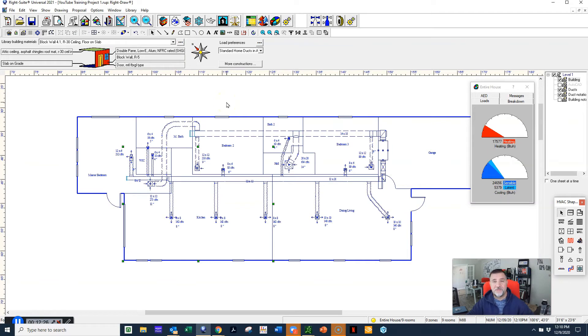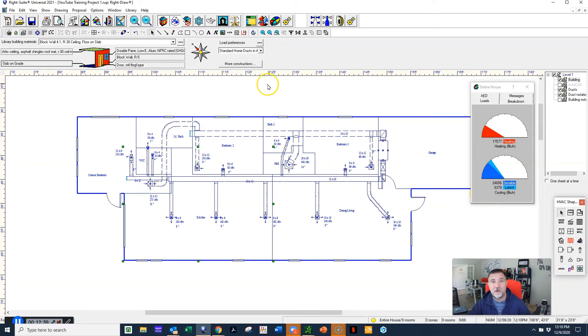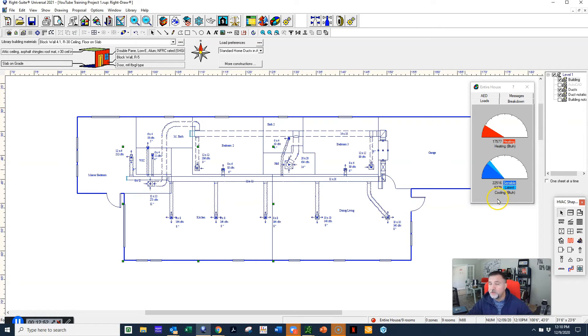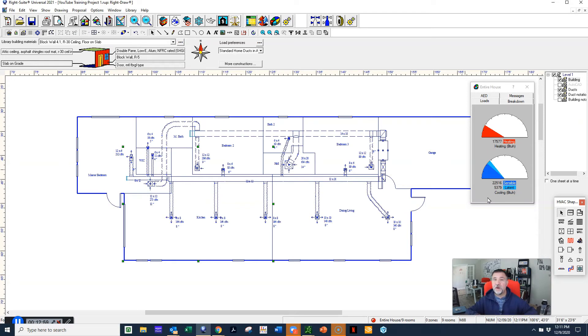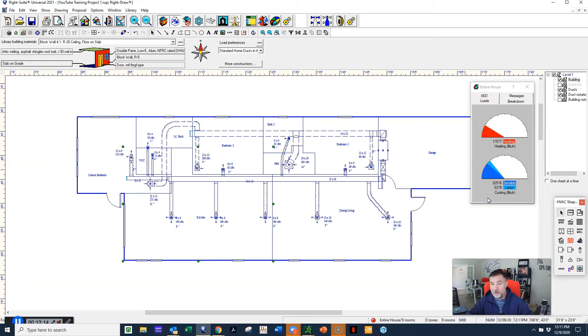Now what if this house faced north-south? Watch this. Right now if we look at our calculation we're at 30,035. Now watch what happens if I change this to where the house faces north or south. Look at that—that was 2,140 BTUs less. Now it's a small house, it's not a big house, but if this was bigger or had more windows, giant sliding glass doors or whatnot on the east-west side, that number will be greater. But 2,100 BTUs could technically be the difference between going from a two-ton to a two-and-a-half or a three to a three-and-a-half, depending on what your load is.